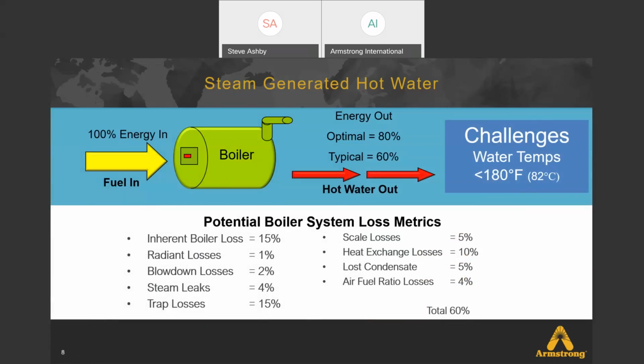So here's how our line of thinking is when we look at using a steam boiler and the efficiency in generating hot water. As you put 100% energy into a boiler, the pretty recognized efficiency is around 80 or 82% of the boiler. However, when you add in other system issues, that efficiency really takes a further dip. And by that, we're talking about inherent boiler loss, radiant losses, blow-down losses, steam leaks, trap losses as far as blow-through traps, scaling within the steam system, heat exchange losses, lost condensate, and air-fuel ratio losses.